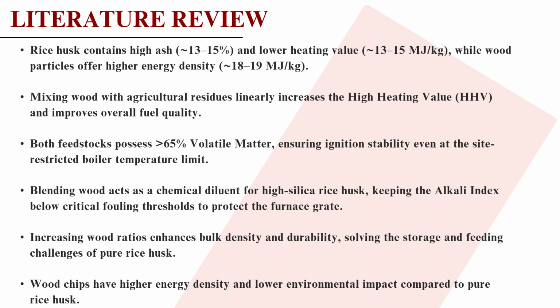Furthermore, blending acts as a chemical shield. It dilutes the high silica in rice husk, keeping the alkali index low enough to protect our furnace grates from melting ash and clinkers. Finally, adding wood improves bulk density, making the fuel easier to store and feed into the system compared to the pure loose husk.